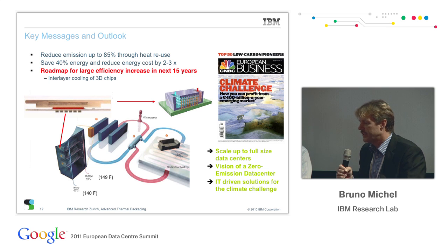The main message is we can save a lot of energy. We can do energy reuse with direct chip cooling, and we have a roadmap for the next 15 years, enabled by chip-level liquid cooling that allows a large compaction of computers. We save energy costs 2 to 3x with direct chip cooling, and we can increase overall computation efficiency by almost a factor of 100 by going to this complexity.